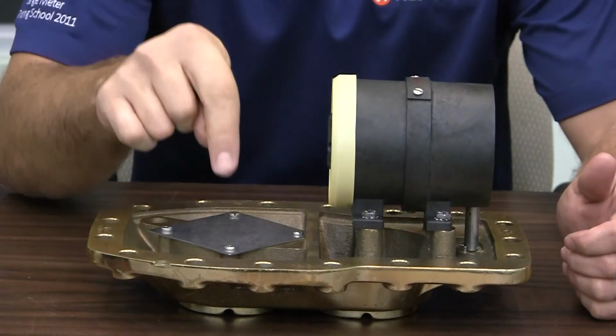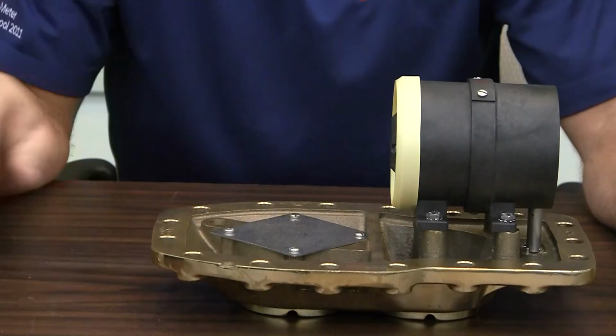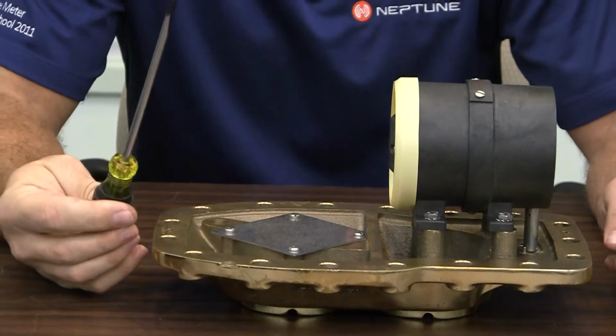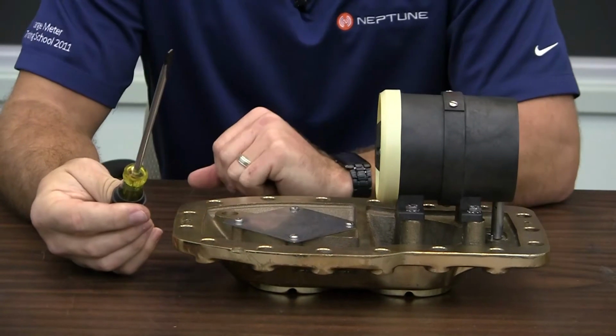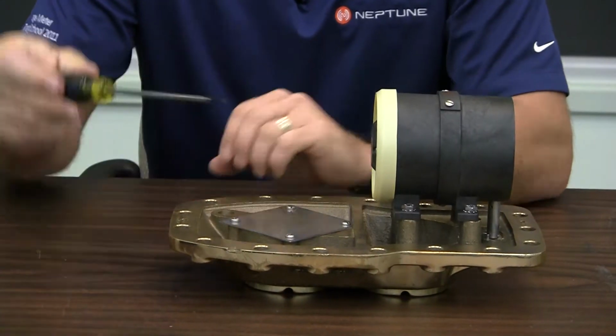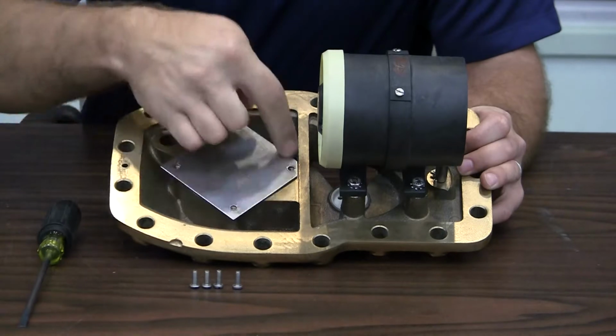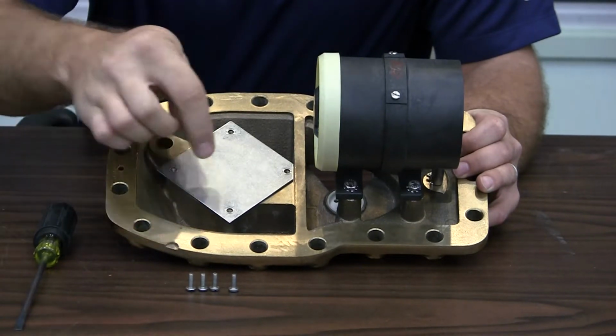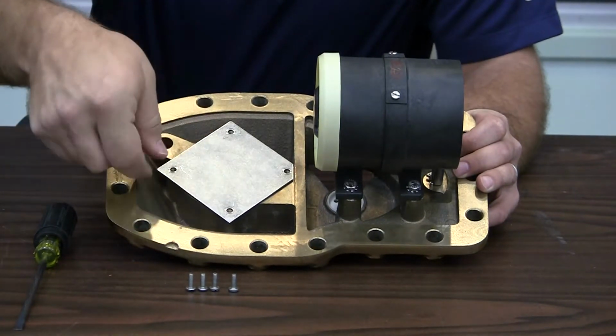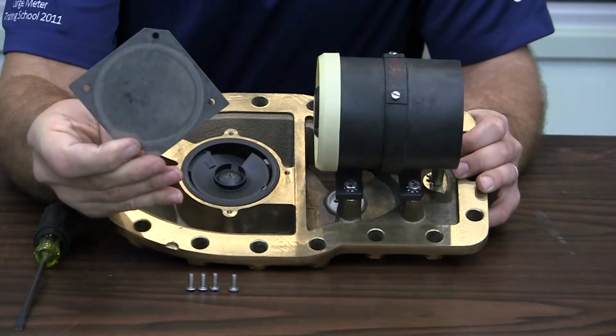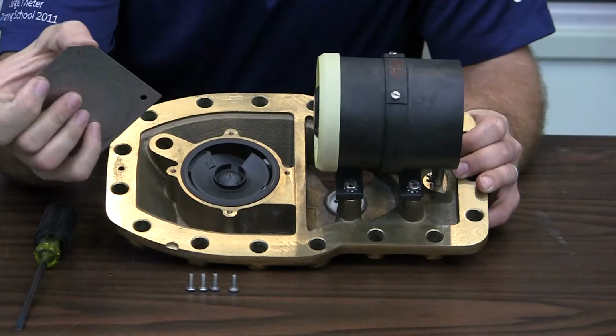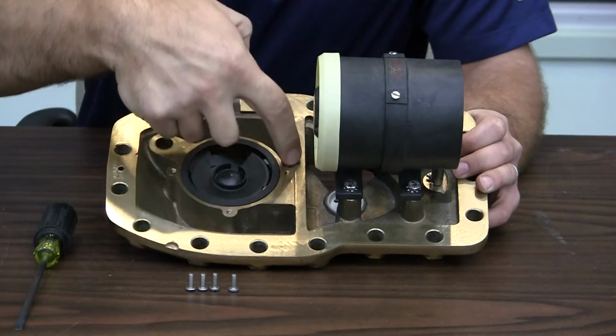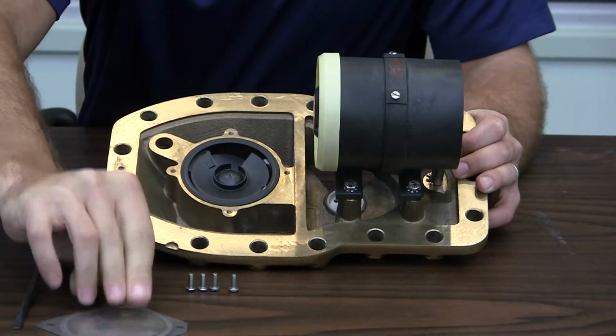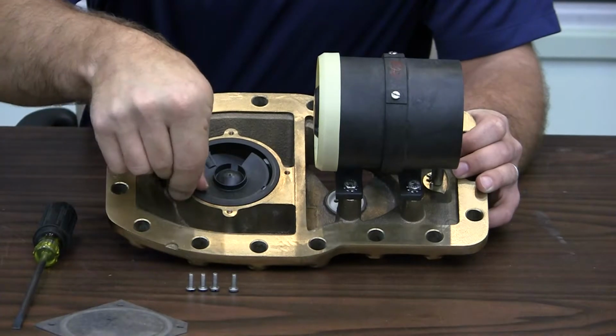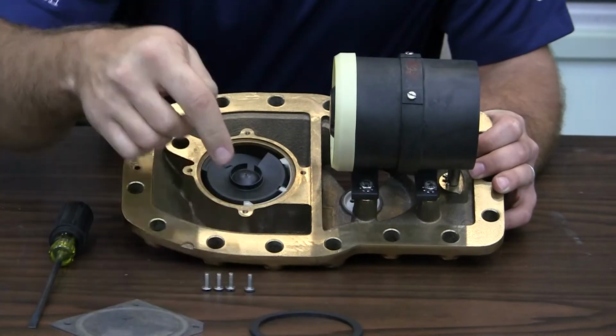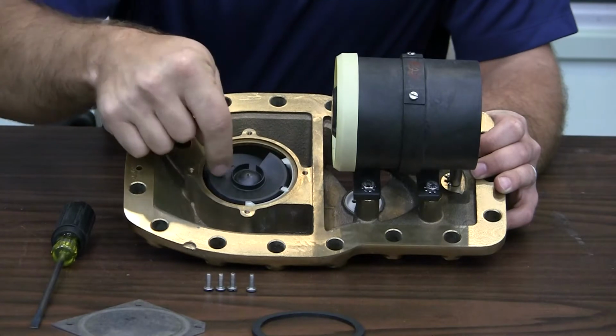First, we're going to remove the disc from the cover assembly. To do so, all you'll need is a flat screwdriver. I'm going to remove the 4 screws, and this will open up and show us the disc portion of the meter. I've removed the 4 screws from the bottom of the chamber plate, rather. And now I should be able to pick this up, and if you can notice, one side is chamfered. This chamfer feature aligns with the bridge portion on the back of the cover. After you remove that, you can expose the rubber gasket. Then you'll see a white strainer and the chamber assembly.